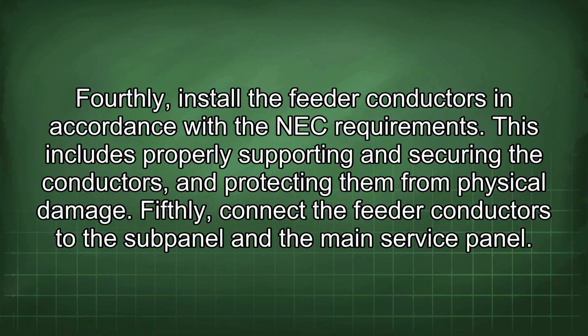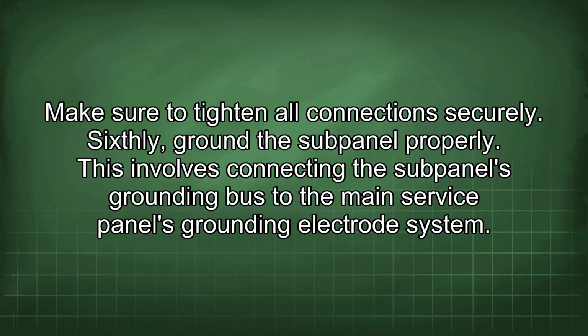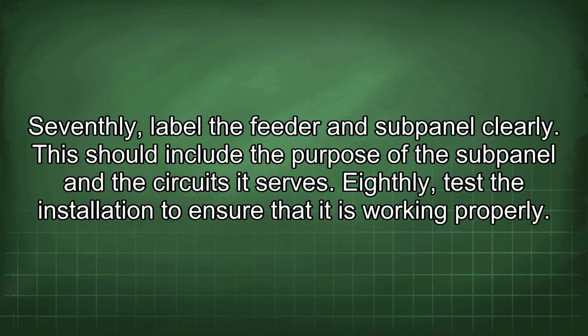Fifthly, connect the feeder conductors to the subpanel and the main service panel. Make sure to tighten all connections securely. Sixthly, ground the subpanel properly. This involves connecting the subpanel's grounding bus to the main service panel's grounding electrode system. Seventhly, label the feeder and subpanel clearly. This should include the purpose of the subpanel and the circuits it serves.